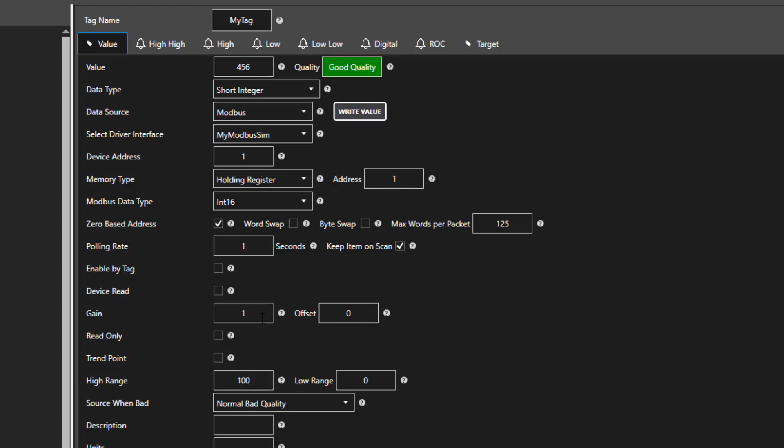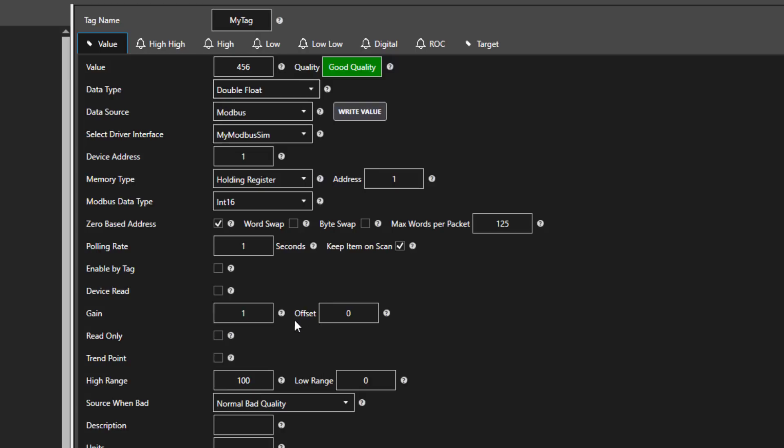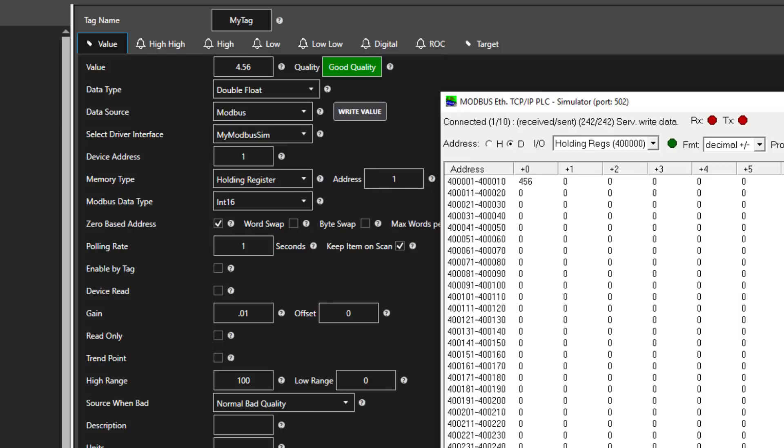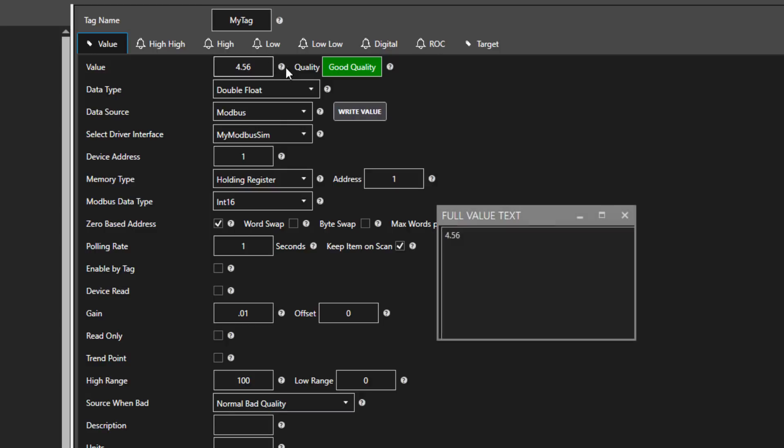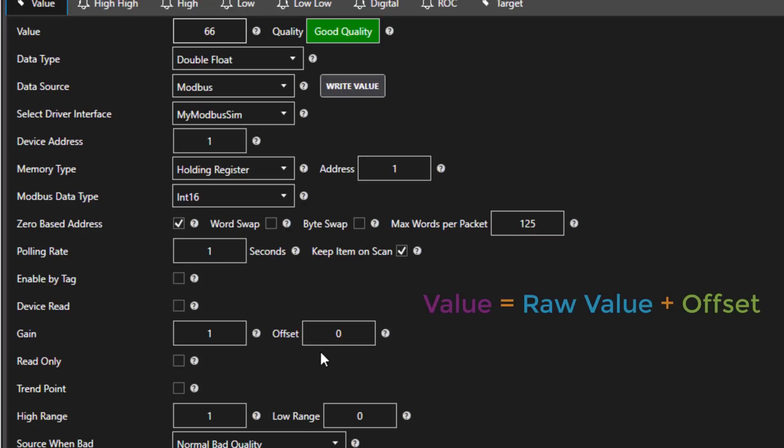You can add a gain or an offset to any of the tags. Let's say we have a Modbus integer value and we want to divide it by 100. We could accomplish this by changing the data type to double float and entering 0.01 in the gain field. This way, whatever value we have coming in is divided by 100. Also, when we write back, if we were to write a value of 0.5, then it also does the appropriate math going back the other way. Setting the offset adds to the value coming in and subtracts when it writes back.